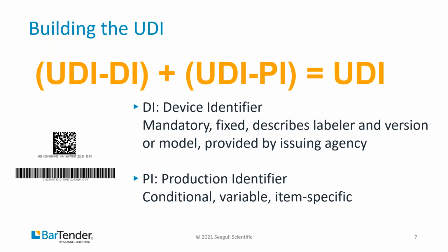Okay. The second part of the UDI is the production identifier, the PI. This will vary from device to device. Each individual item will have its own individual PI. The PI is the conditional variable portion of the UDI created by the manufacturer. It contains internal tracking information. So the lot or batch number within which a device was manufactured, maybe serial number, expiration date of a specific device, the date a device was manufactured.